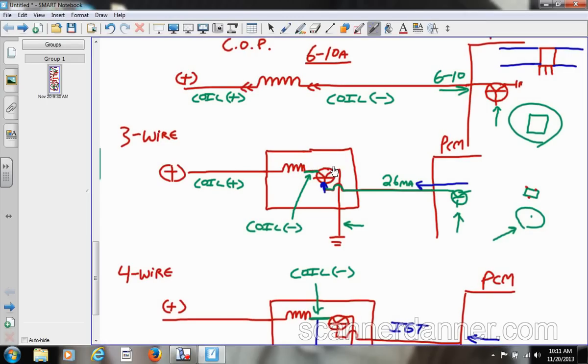Can I view a turn on signal here? Of course, it's a low voltage, generally 0 to 4 volt signal. That's not coil negative voltage. Can I look at coil negative voltage here? Of course, but are you going to see those pressure changes on a ground wire? No, it's a ground, this is after the effect.